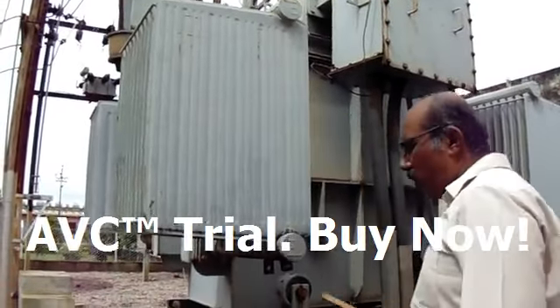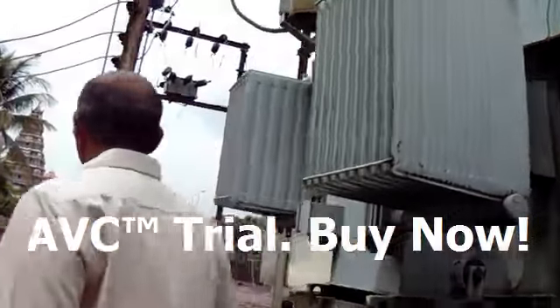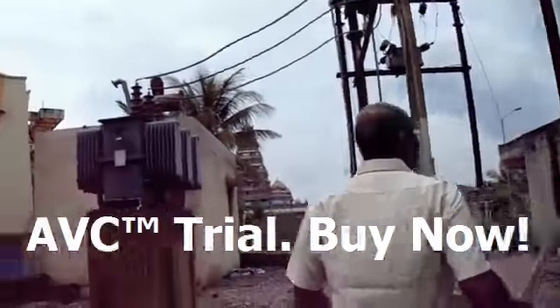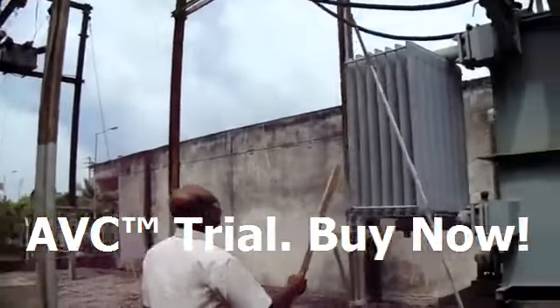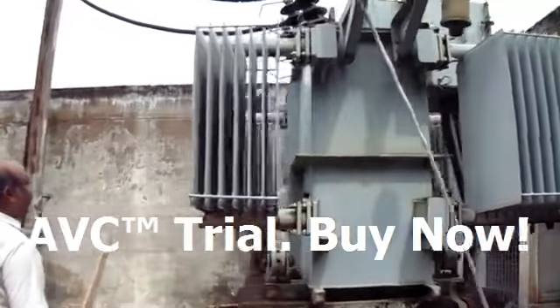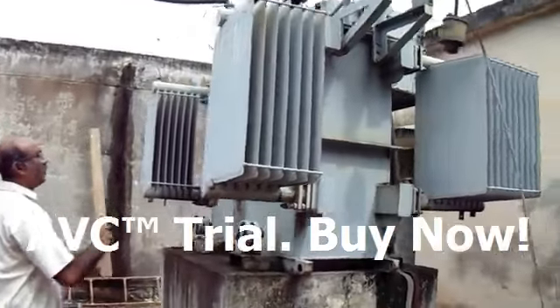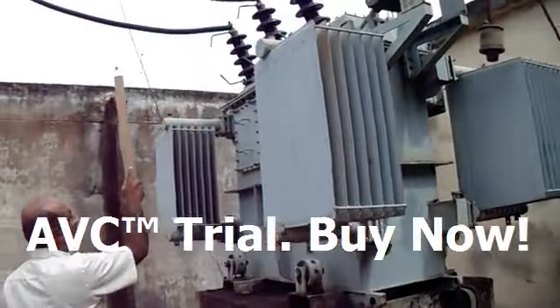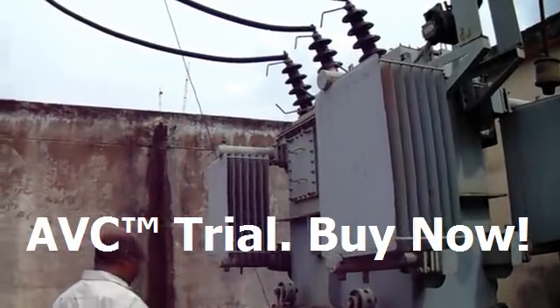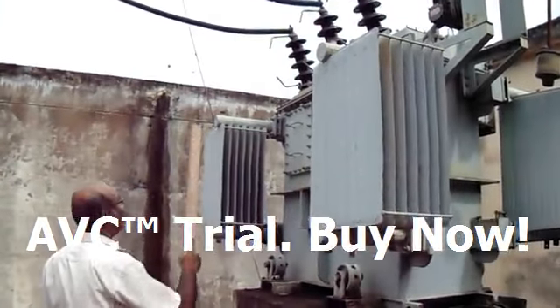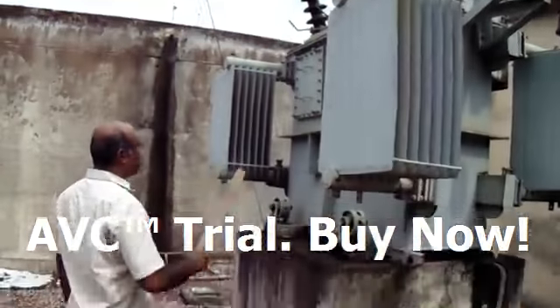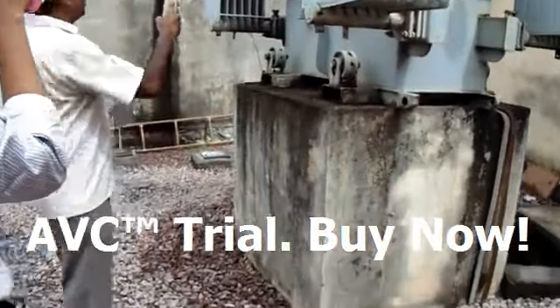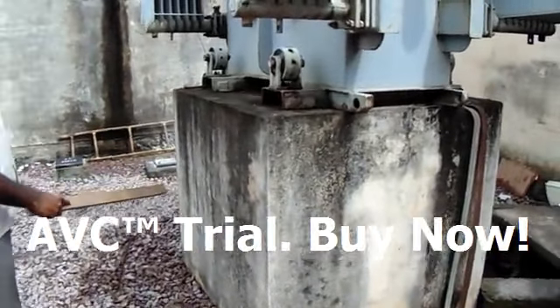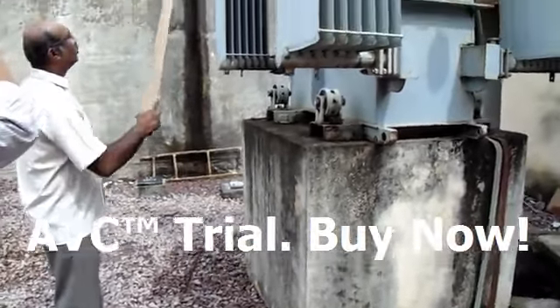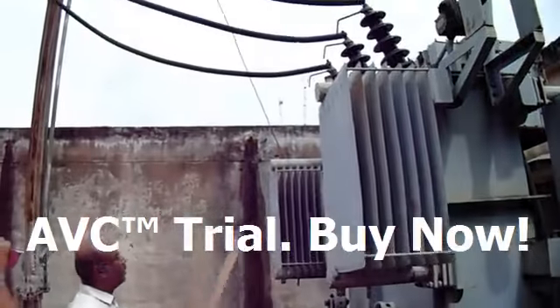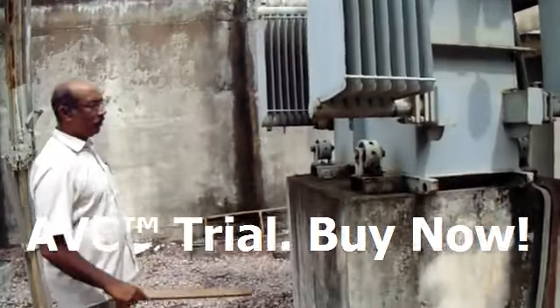If you come to the HT side, as per the safety measures, the height of the HT bushing from the ground level should be 2.8 meters, so that even if I am standing here with a stick in my hand, it should not touch the HT wires. From the ground level to the HT top bushing, when you mount this transformer on this plate, the height should be at least 2.5 meters. As per the safety standard, it should be more than 2.5 meters. We have kept it here at 2.8 meters.